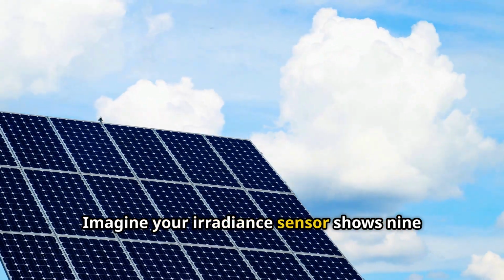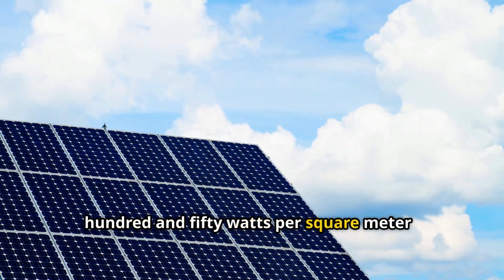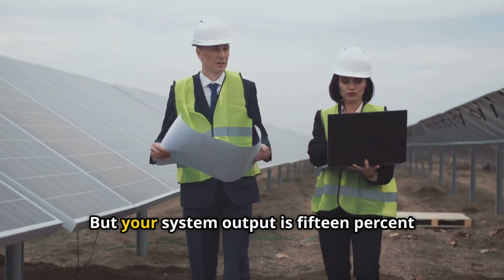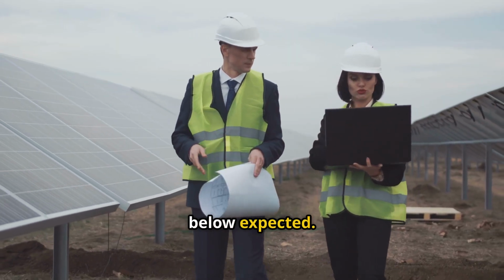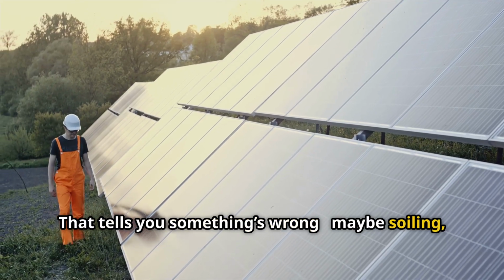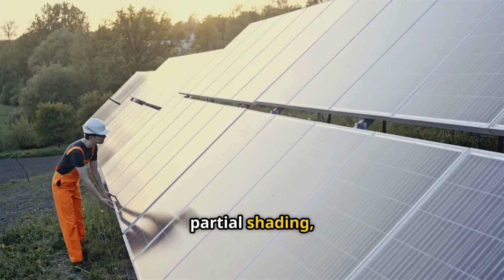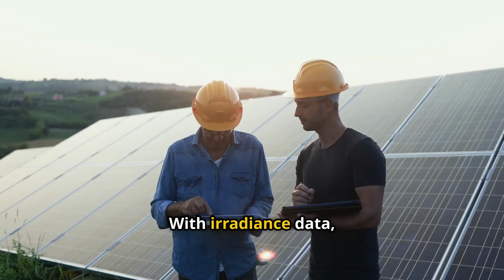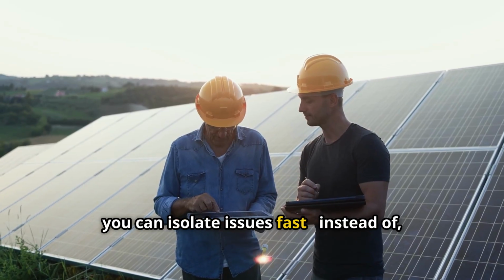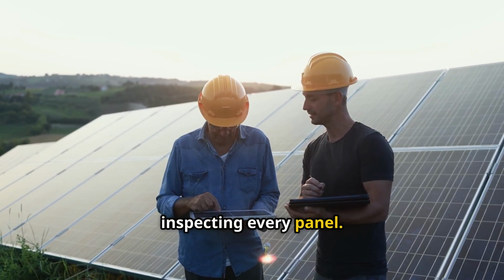Imagine your irradiance sensor shows 950 watts per square meter, a strong sunlight level, but your system output is 15% below expected. That tells you something's wrong, maybe soiling, partial shading, or a malfunctioning string. With irradiance data, you can isolate issues fast instead of inspecting every panel.